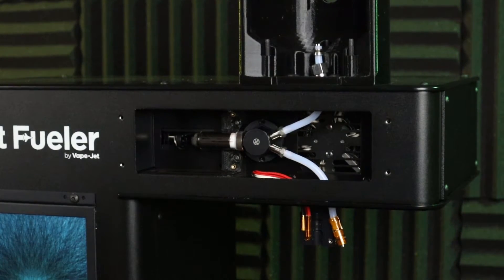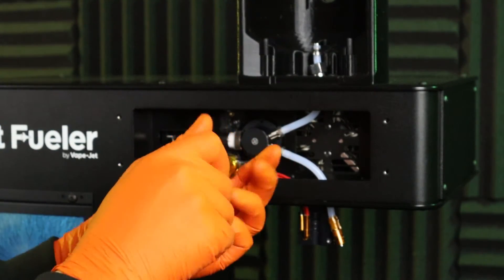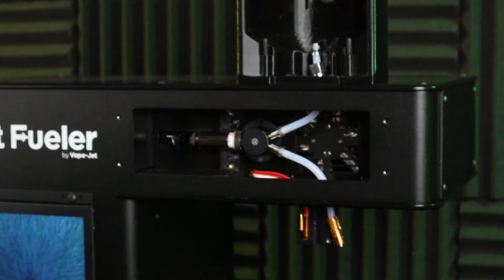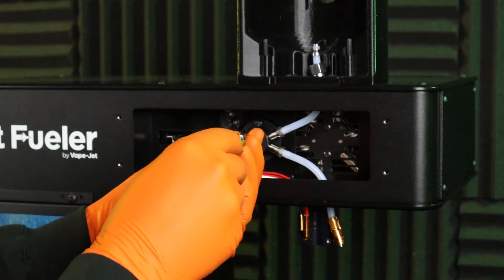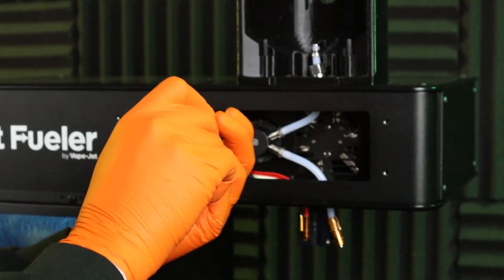Reinsert the M3 by 12 millimeter hexagonal screws into the valve body and tighten using the 2.5 millimeter hexagonal driver. Do not over tighten these screws. The threads in the pump housing may strip. Stripped mounting holes will prevent normal operation and cannot be repaired.